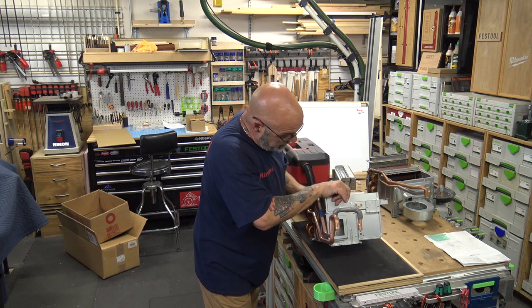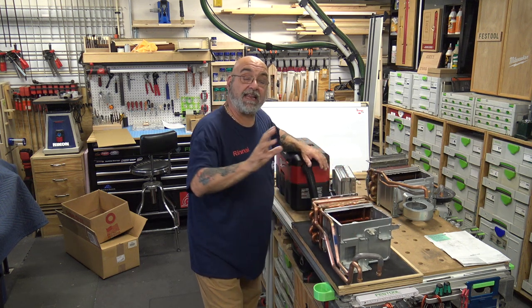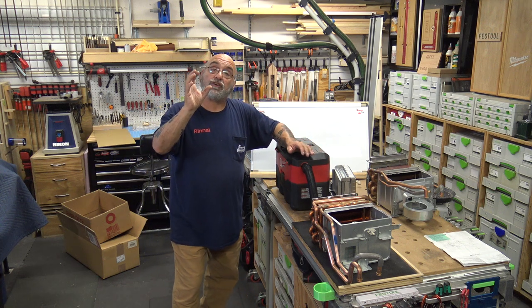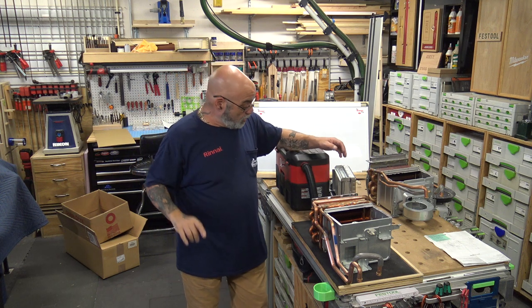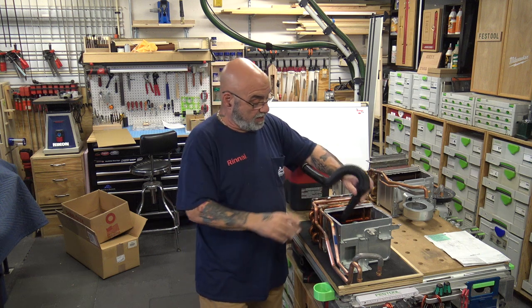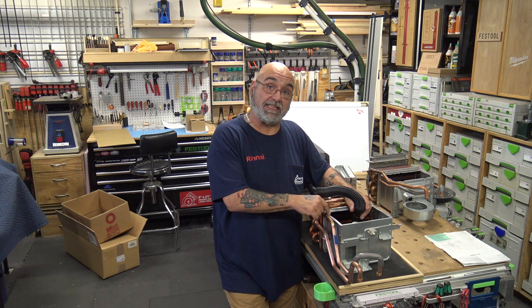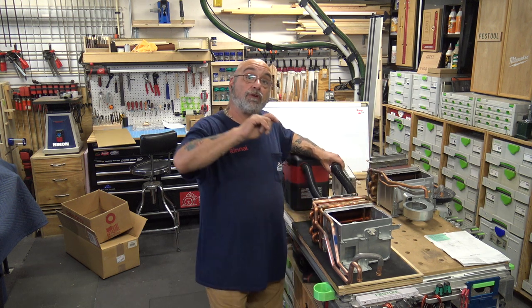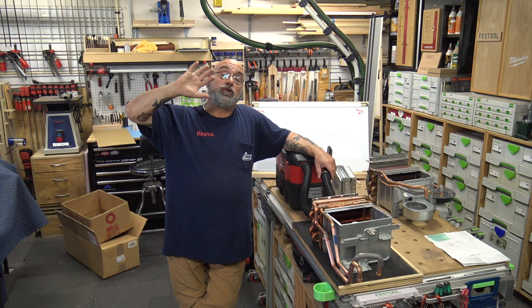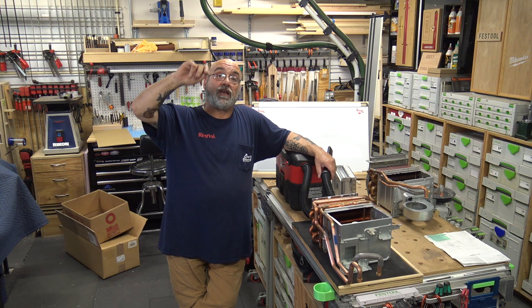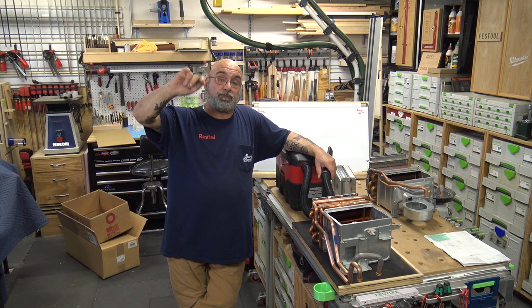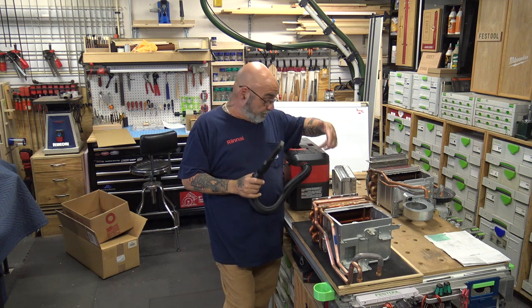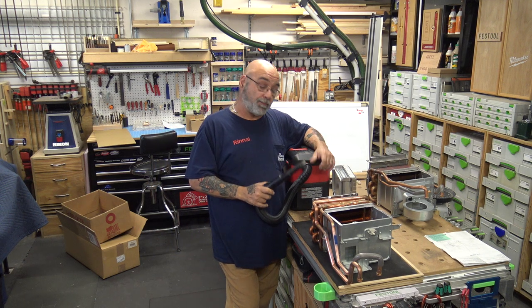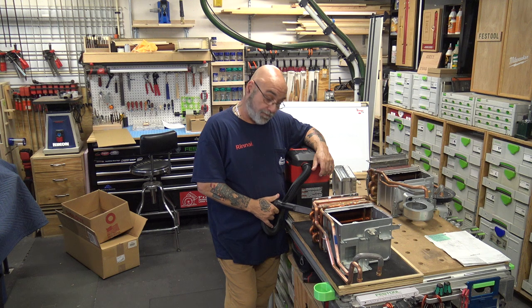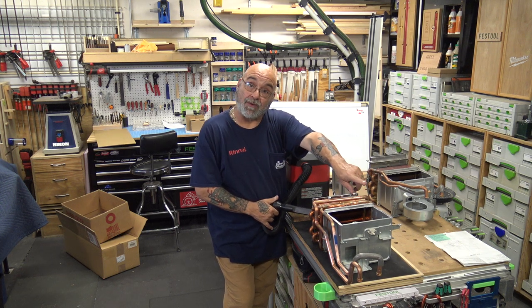You want to get up in this heat exchanger with that vacuum brush attachment. Remember, you don't want to stick your wand up in here and start messing around with it, because you're going to bend the fins. If that happens, you're going to have to put a brush in there. Use a soft bristle brass brush and blow it out very easy. You might have to reverse the vacuum or your compressor and blow air from the top down out.